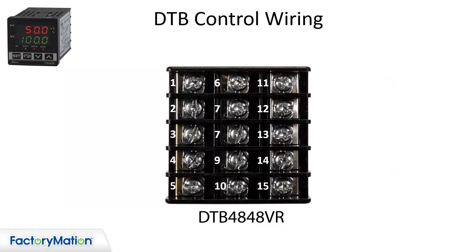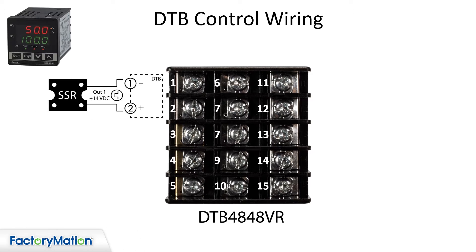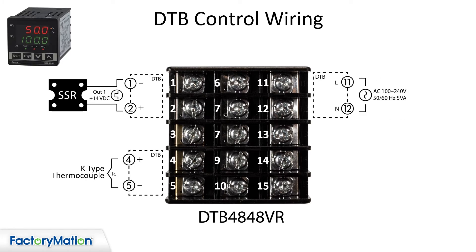This example uses a DTB 4848VR. Connect a solid state relay to output terminals 1 and 2. Connect the thermocouple to terminals 4 and 5. Connect the incoming AC power to terminals 11 and 12.